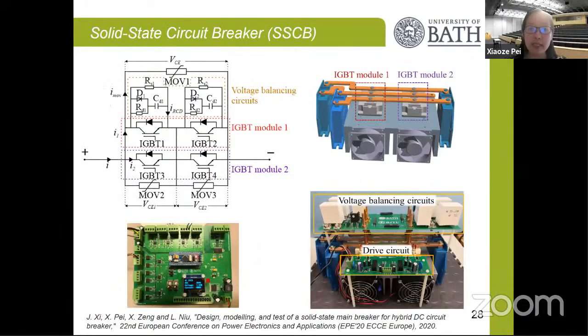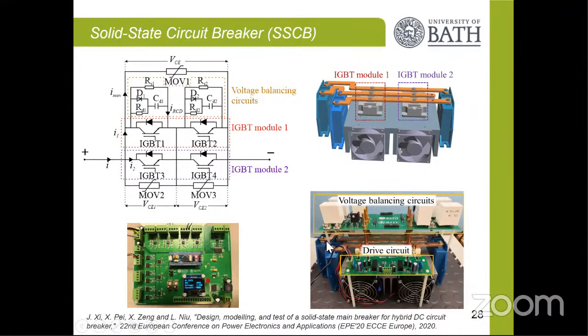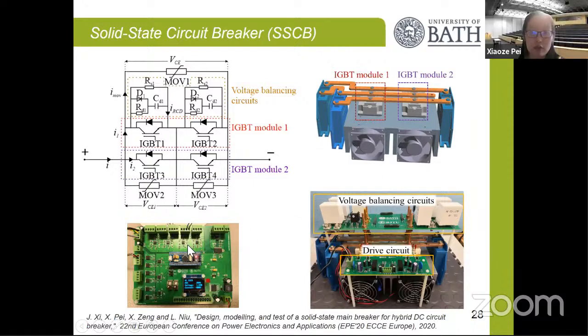The second area is the solid state circuit breaker. We designed a prototype that has 2 IGBTs connected in series and 2 IGBT modules connected in parallel. With this system we are able to investigate the current sharing during normal operation and the voltage sharing during the interruption. Are we able to have a balanced system design? We have built a prototype in the lab, and this is a 3D design and a control circuit.